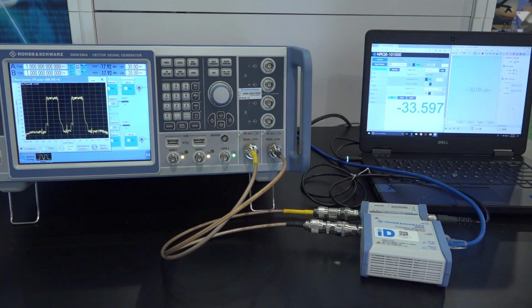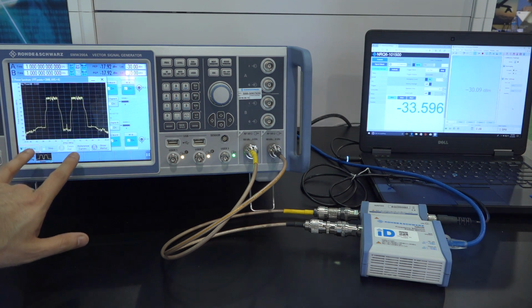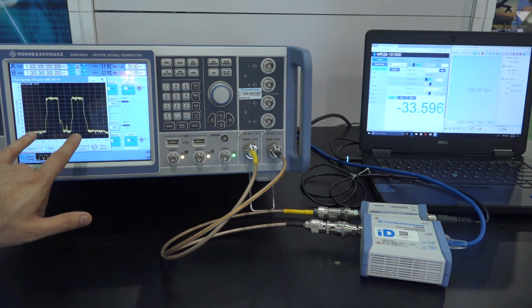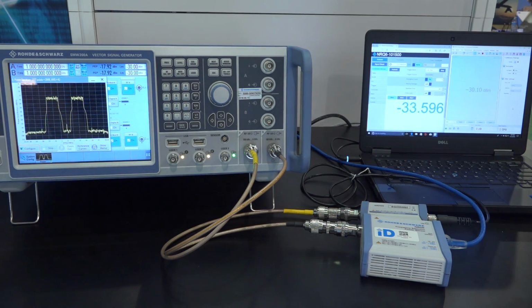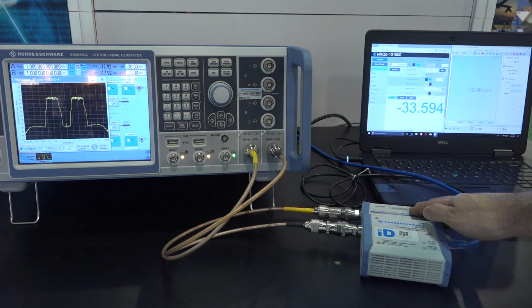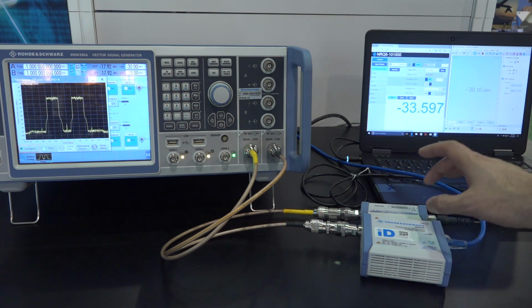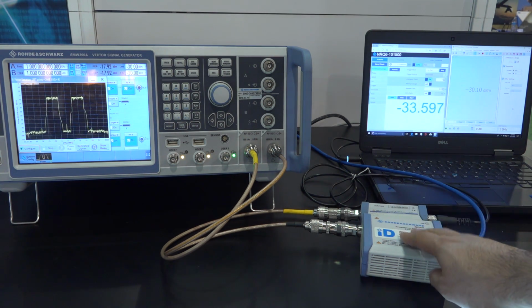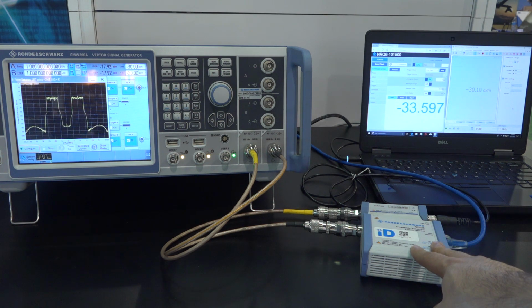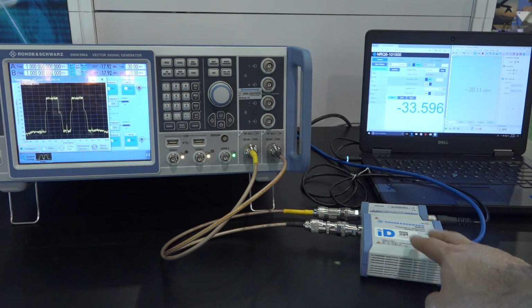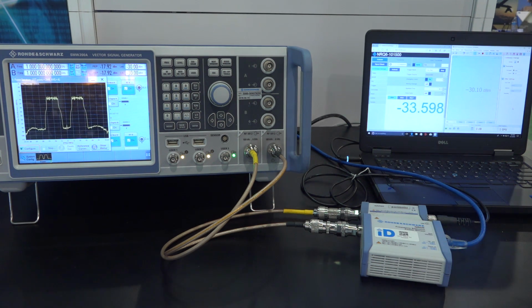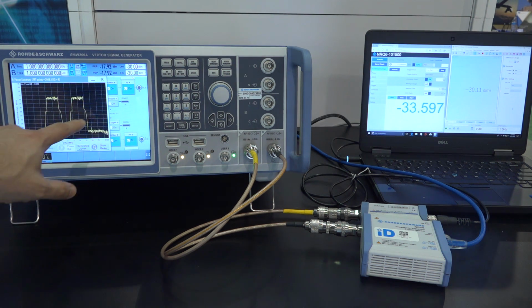So this is exactly what this product does. Here they're feeding two signals, two channels of very close signals to each other, to both of these sensors at the same time. So this sensor over here is seeing both of those at the same time, but the new sensor is able to have a channel as wide as 100 megahertz and as narrow as 1 megahertz. So you can select exactly which of the power of these two channels you want to measure without the other one interfering.